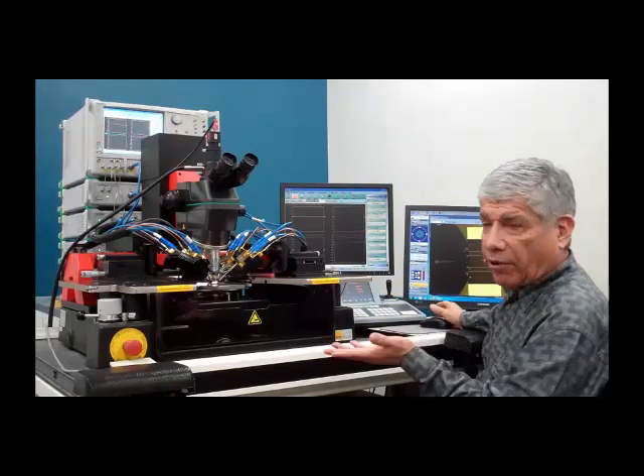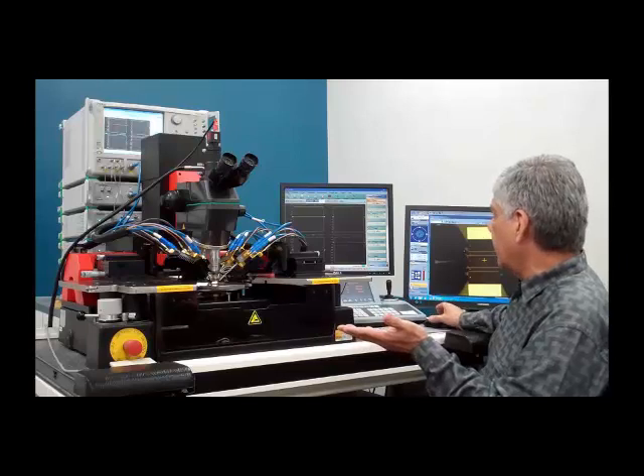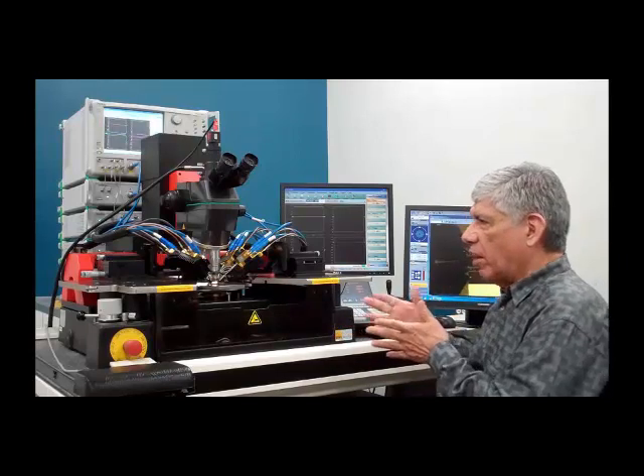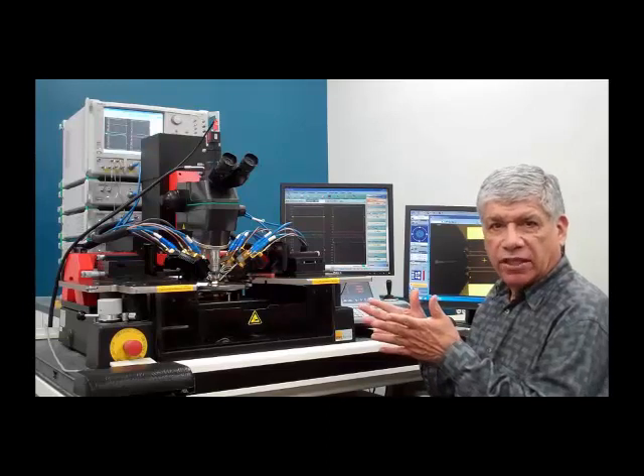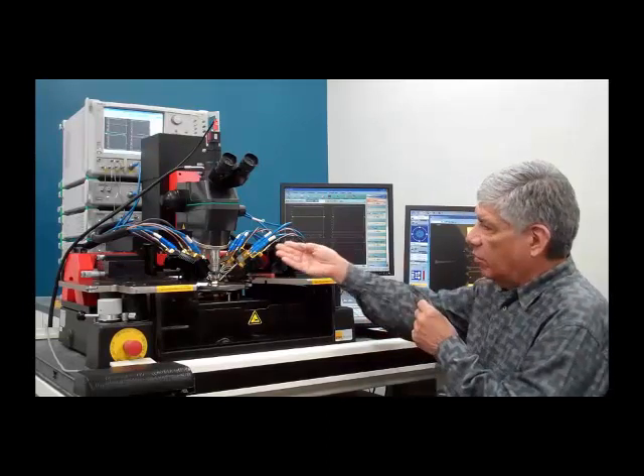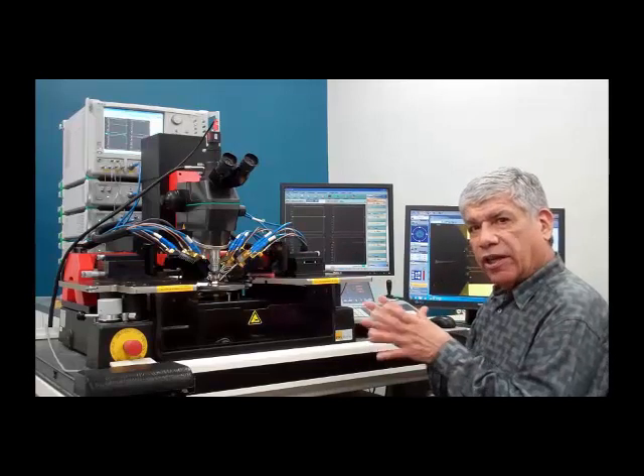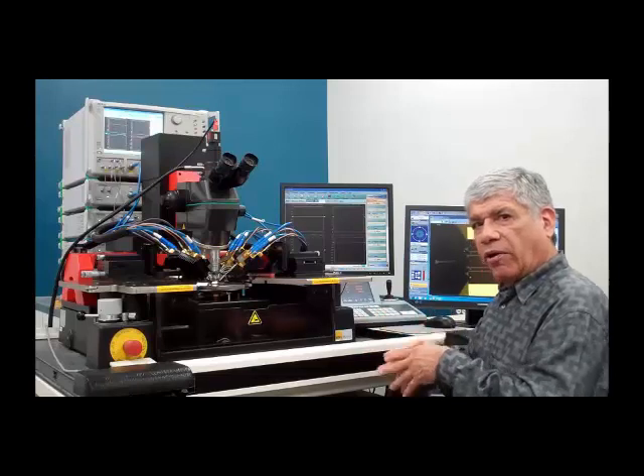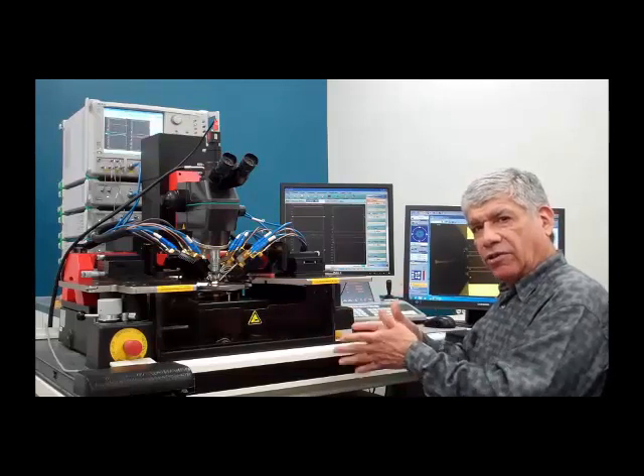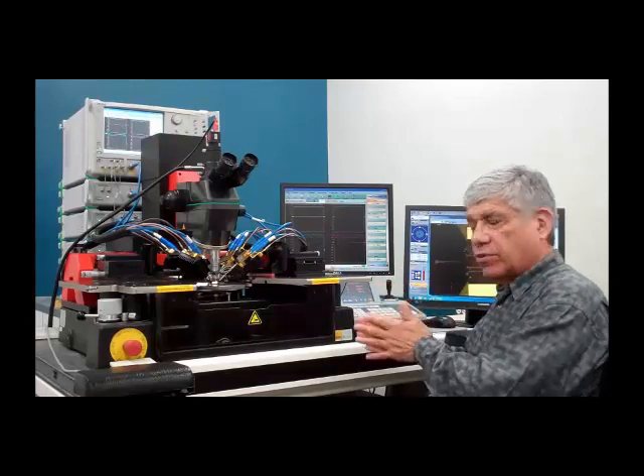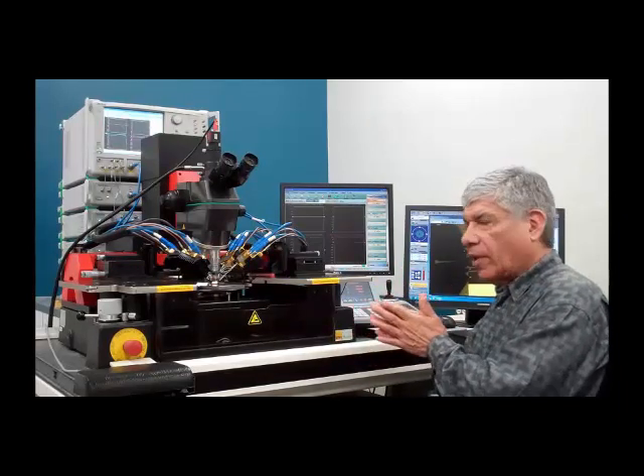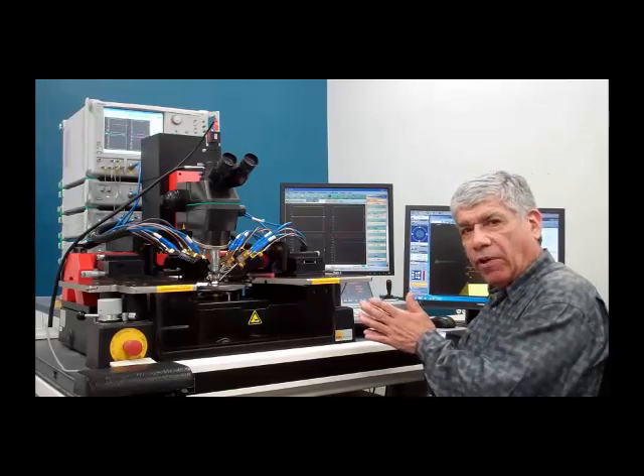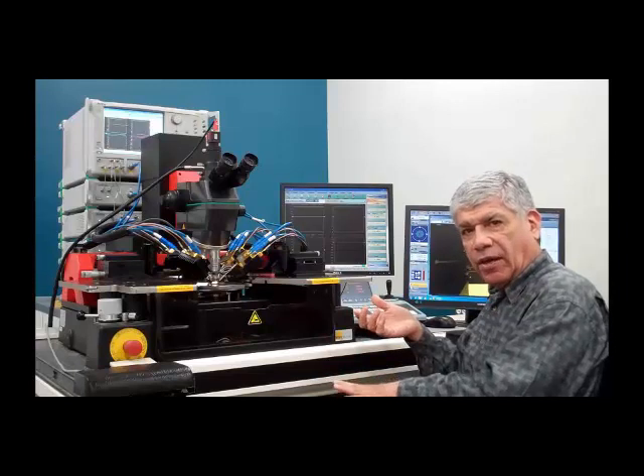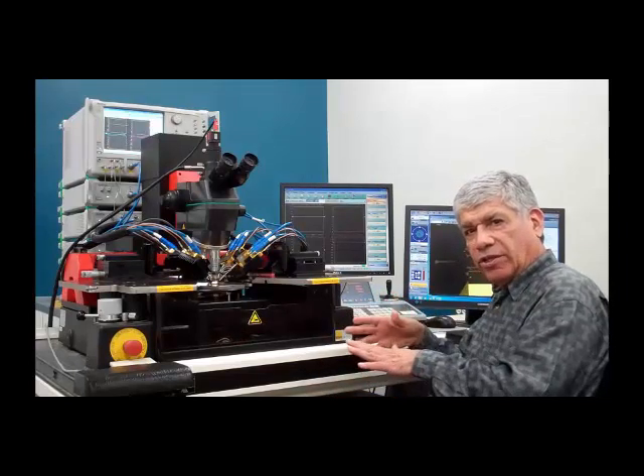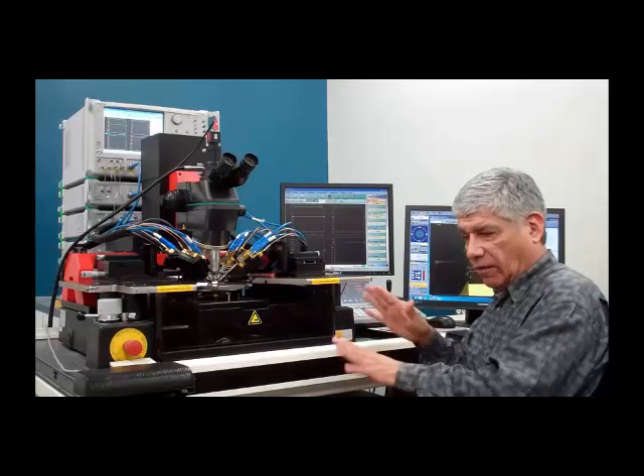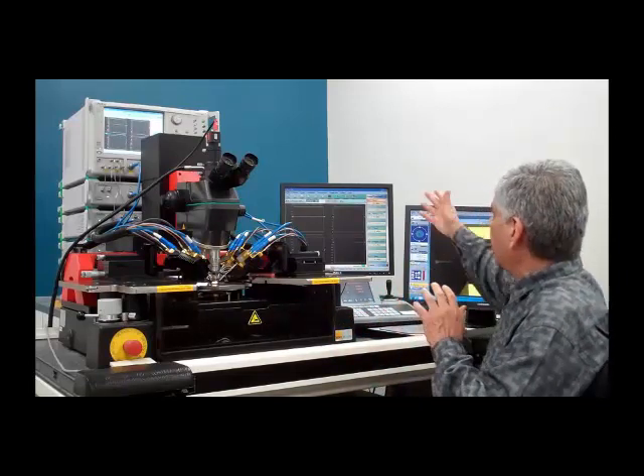Next, we would set up the power, and in this case, I have minus 15 dBm. We can do anywhere from about minus 10 to minus 50, minus 55 dBm. So in the millimeter wave modules, we have an electronic ALC control. So we are actively engaging in ALC power leveling as we're sweeping. We don't need lookup tables, etc. And with the wide range of control that we have, we can get it all the way down to minus 50 dBm or even lower in order to measure very sensitive devices at very low power levels. Okay, so the power we have now set.